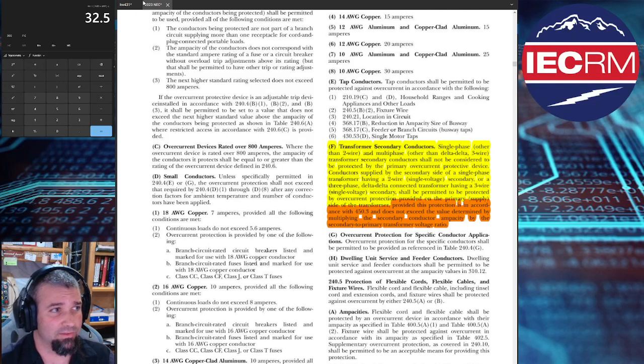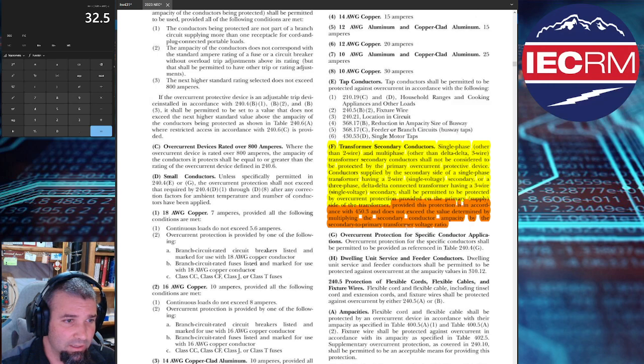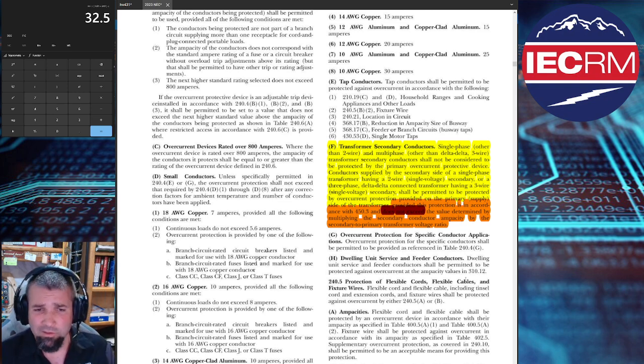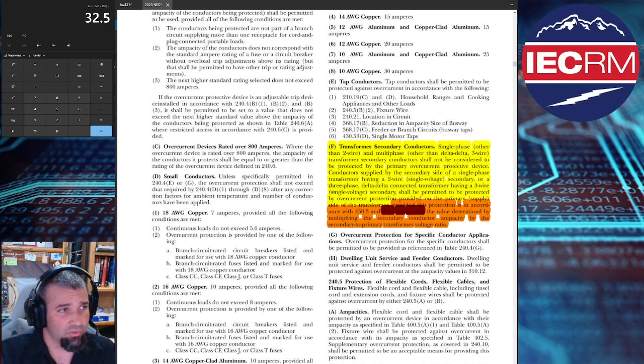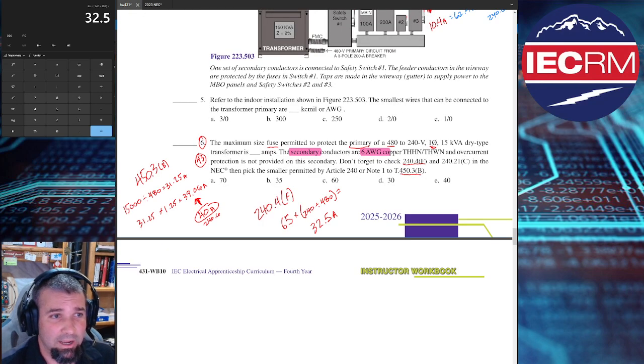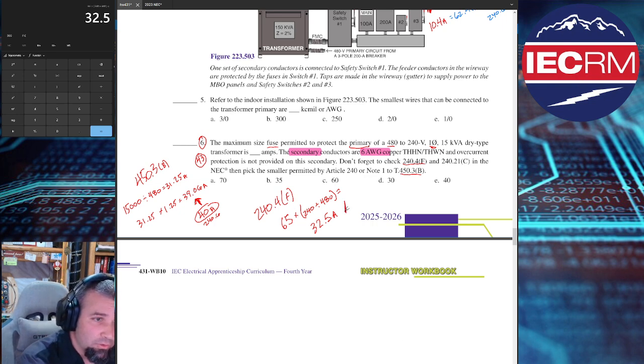This is where I have to get crazy with the highlighter. Let's get another color here. Okay. 32.5. That doesn't land on something. Okay. This says specifically inside of here, does not exceed. Does not exceed. What that means is we have to round down. Okay. Does not exceed. You got it, Simon, 100%. So we are going to round that down because we cannot go over 32.5 amps. So we will round that down to our next standard size of 30 amperes.